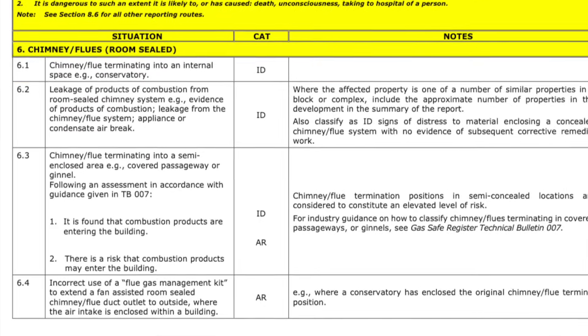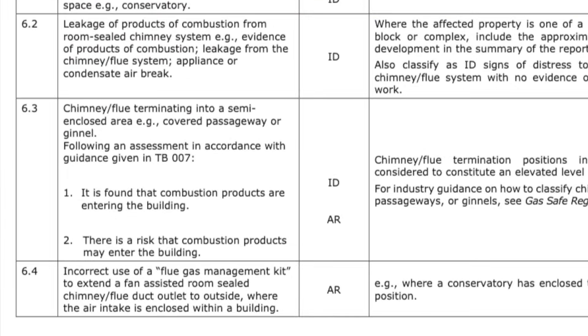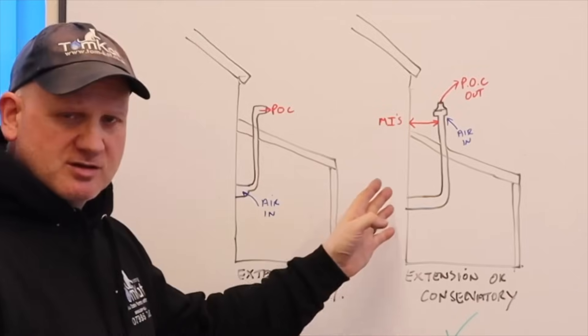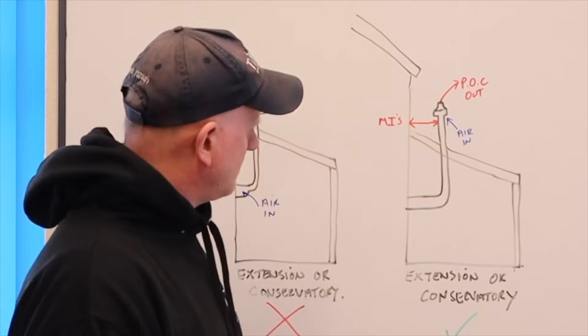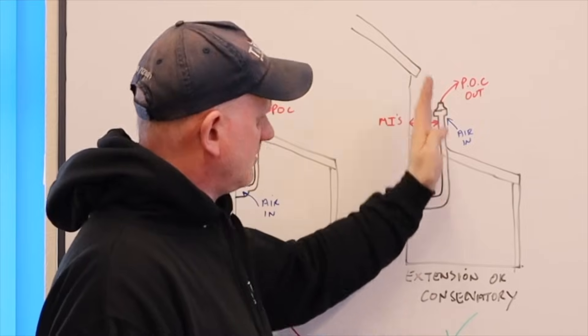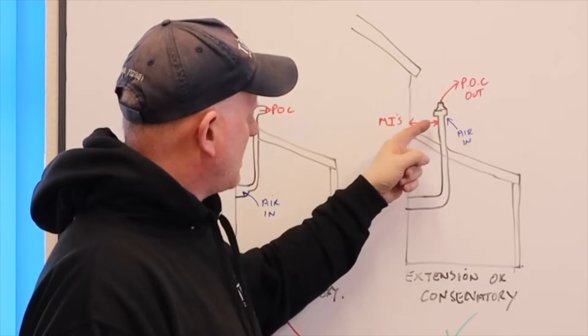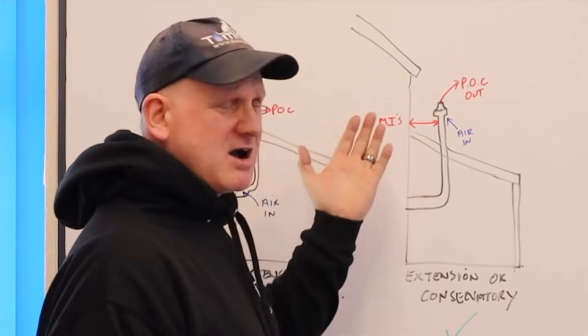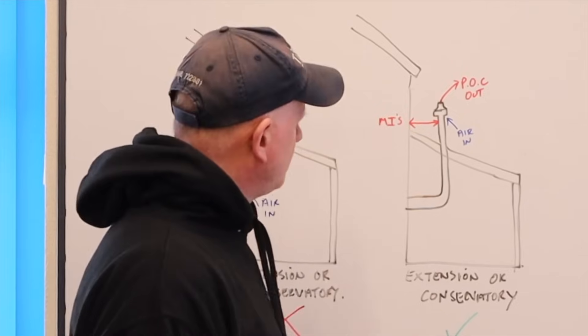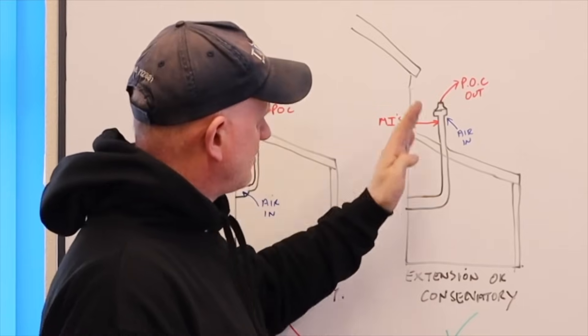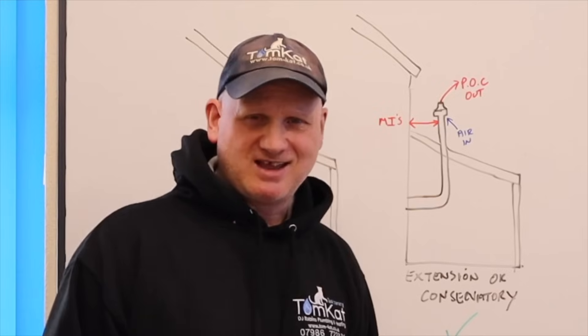That would be classed as at risk, under iGEM G11, the unsafe situations procedure. But, this is what you would have to do. You would have to take the flue through on a vertical flue system and you would have a distance of whatever the manufacturer's instruction says. Now, I've seen this as little as 300 up to 1,500. So, you would follow the manufacturer's instructions and you would use a vertical kit.